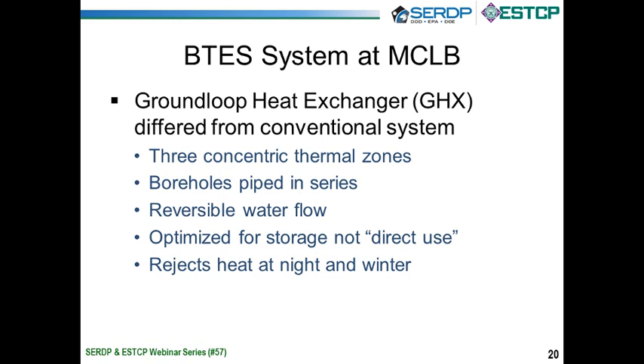The BTES system at Albany involved a ground loop heat exchanger, and that's typically in the United States, in most places, constructed of high-density polyethylene pipe, so-called HDPE, that's grouted down into a borehole, the borehole going down anywhere typically 150 to 600 feet. At Albany, it was 210 feet deep and 306 boreholes that we drilled there.